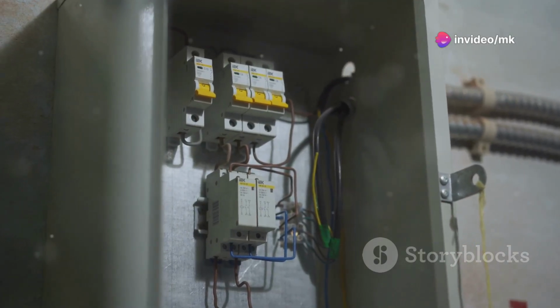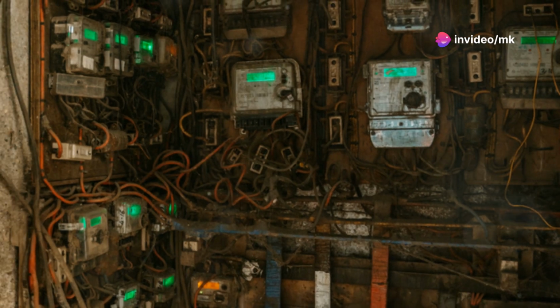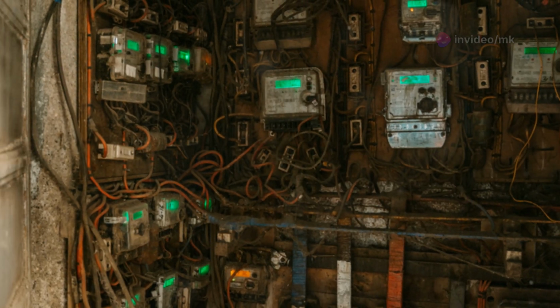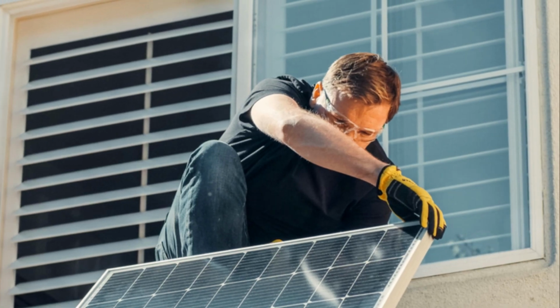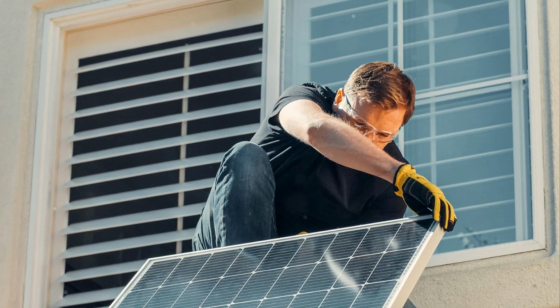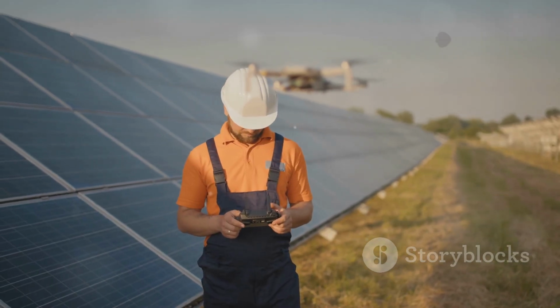And finally, a main DC isolator switch. This is our big off switch for the entire solar array, usually near the inverter, also rated 500 to 600 volts and 20 to 32 amps. Oh, and just a heads up, some inverters actually have this built in.